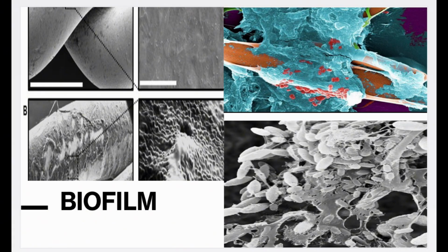Understanding the difference between bioburden and biofilm helps explain why every stage of instrument reprocessing matters. Point of use treatment matters, transportation, cleaning materials, water quality, detergent concentration, temperature matters, contact time matters, mechanical action, inspection, and following the manufacturer's IFU matters.